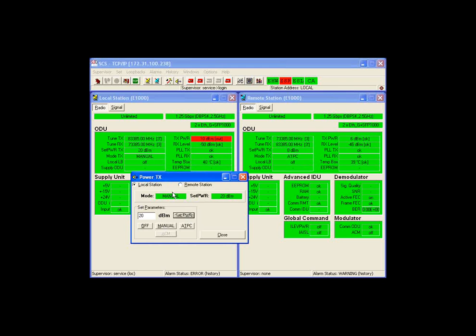Now you see what was changed. Set power TX is set to maximum 20 dB. In this case 20 dB is the maximum, the technical limit of the device, and ATPC is automatically controlling the level of the signal. On the opposite side I am for some reason on 8 dB, but I can do the same: go to power TX, set manual... sorry, I have to first switch to this one. Set manual, set 20, and activate ATPC. Now the system is configured for full, how to say, maximum availability, because ATPC is set to 20 dB and the system is increasing or decreasing power based on these requirements.